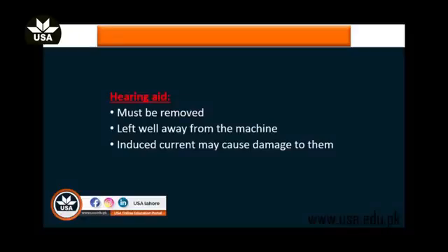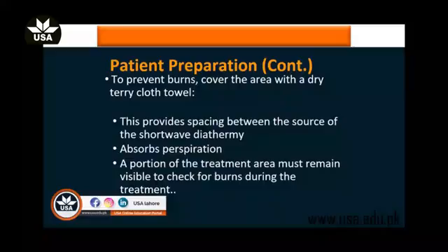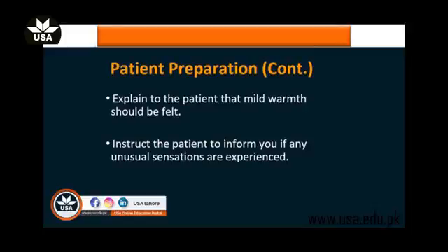Hearing aids must also be removed and left well away from the machine, as induced currents may damage them. In order to prevent burns, cover the area with a dry terry towel, which provides spacing between the source of the short-wave diathermy and the skin and absorbs perspiration. A portion of the treatment area must remain visible to check for burns during the treatment. Always explain to the patient that they are going to feel mild warmth, and instruct the patient to inform you if they experience any unusual sensation.